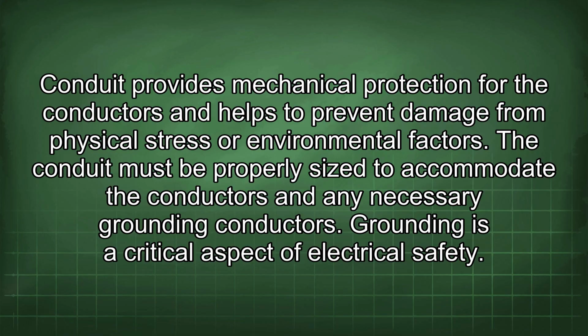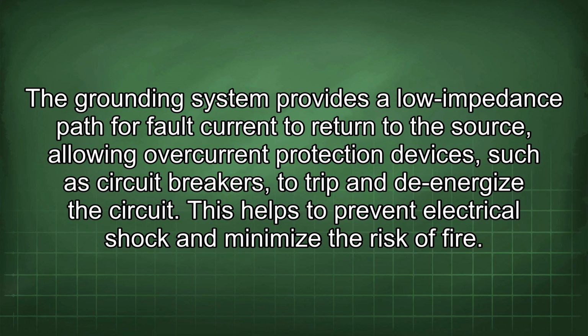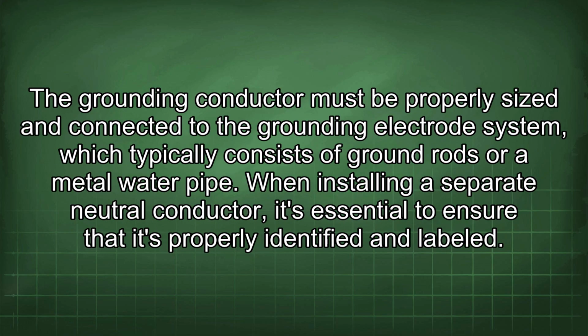Grounding is a critical aspect of electrical safety. The grounding system provides a low impedance path for fault current to return to the source, allowing overcurrent protection devices, such as circuit breakers, to trip and de-energize the circuit. This helps to prevent electrical shock and minimize the risk of fire. The grounding conductor must be properly sized and connected to the grounding electrode system, which typically consists of ground rods or a metal water pipe.